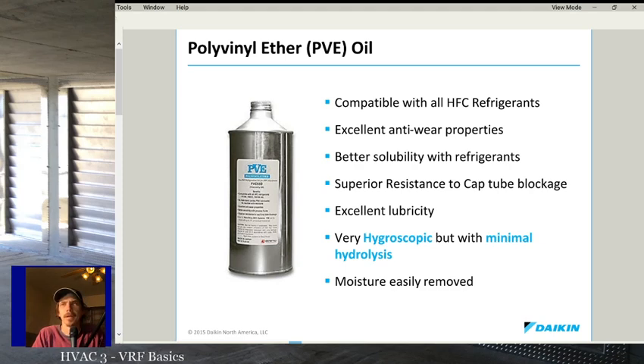All right. PVE oil is way more hygroscopic than POE. So as soon as you open it up, you're going to get a lot of moisture in that oil, and there's going to be nothing you can do about it at that point in time. It's just going to attract any moisture in the air very, very quickly. But the thing is, with PVE, you have minimal hydrolysis with it, right? It's very hygroscopic, but with minimal hydrolysis. So you're going to have less issues with that oil forming an acid quickly.